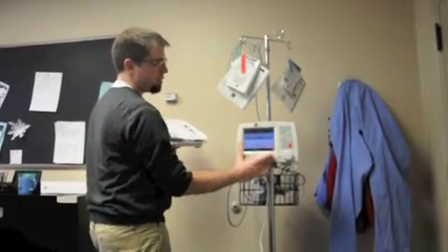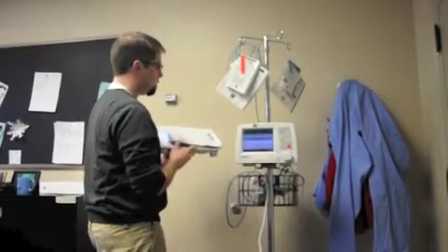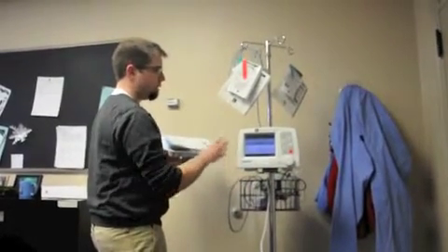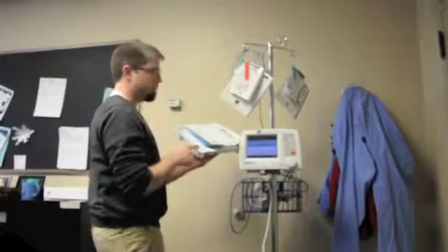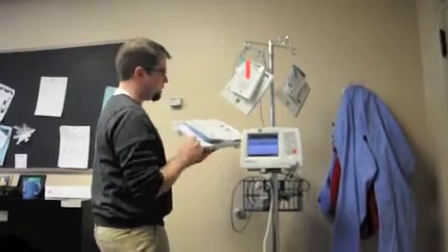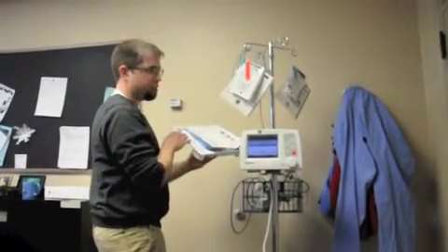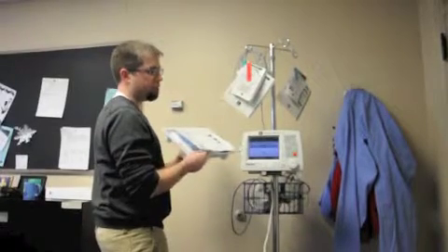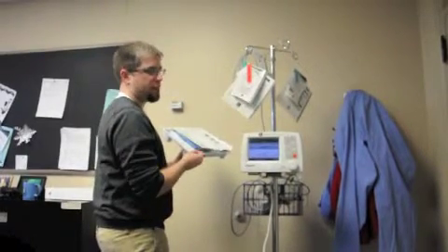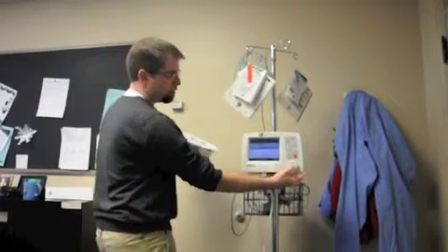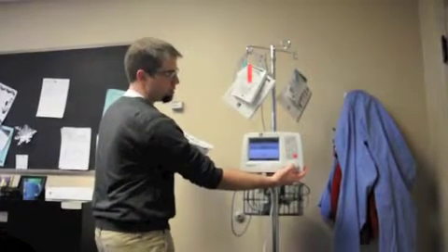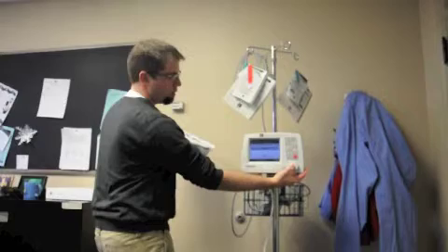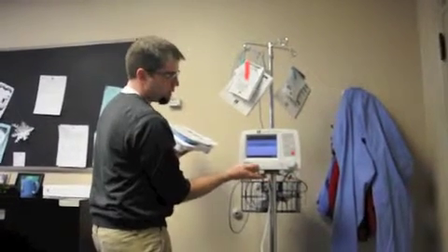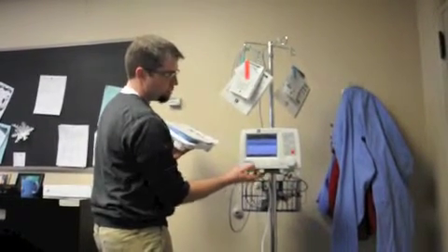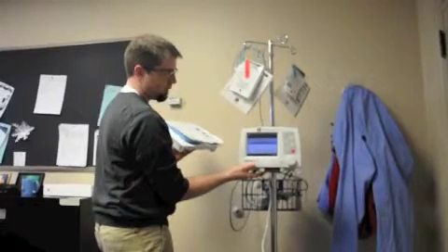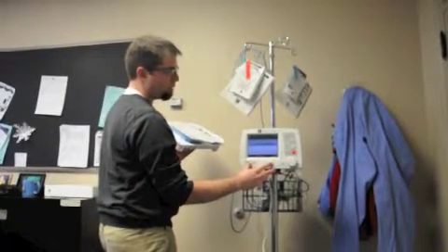So at this point we don't touch anything else on the machine. The physician would have inserted the catheter. Everything is already hooked up to the optical module. We just have to ensure that sterile field is maintained. Usually the physician will have us hold the optical module so it does not interfere with their sterile field. Once the line is inserted, the physician will ask for the value. We hit start, and at this time it's going to run through and actually do the update. And then we will get a lab value.